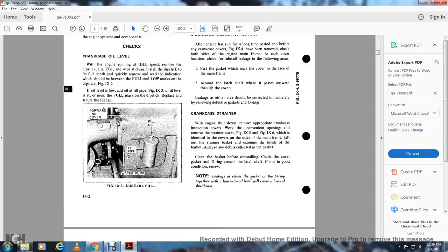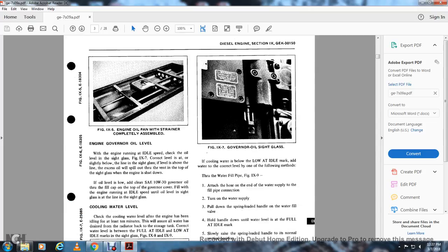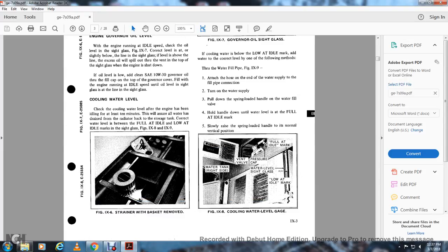Figure 9-5 shows the engine oil pan with the strainer completely assembled. Engine governor oil level: with the engine running at idle speed, check the oil level at the sight glass (figure 9-7). The correct level is at the line in the sight glass. If the level is above the line, excess oil will spill out through the vent at the top of the sight glass. With the engine shut down, if the oil level is low, add clean SAE 10W-30 oil through the fill cap at the top of the governor cover. Fill with the engine running at idle speed until the oil level is at the line in the sight glass.